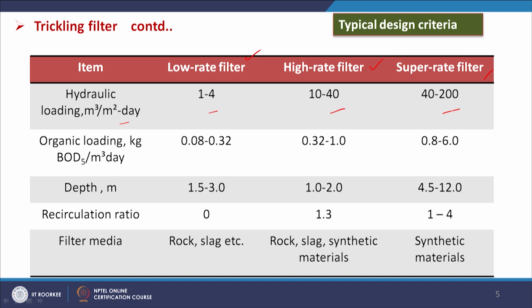Organic loading in kg per cubic meter per day is 0.08 to 0.32 for low rate, 0.32 to 1.0 for high rate, and 0.8 to 6 for super rate — so the organic loading rate is very high. Depth ranges are 1.5 to 3 meters for low rate, 1 to 2 meters for high rate, and 4.5 to 12 meters for super rate. Recirculation ratio is more in the super rate filter, lower for high rate, and negligible for low rate.